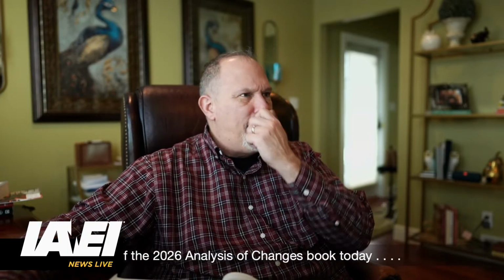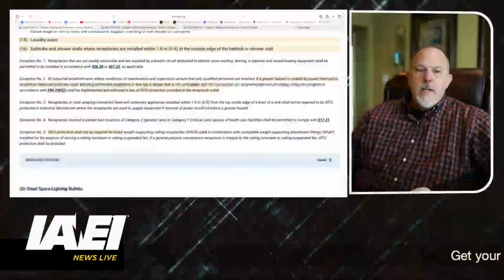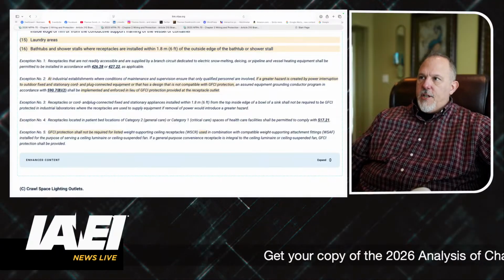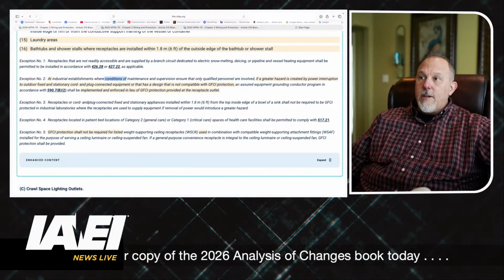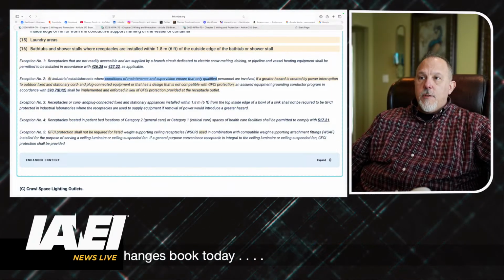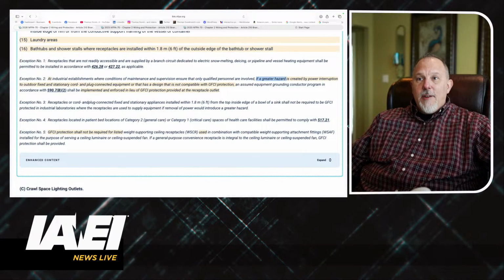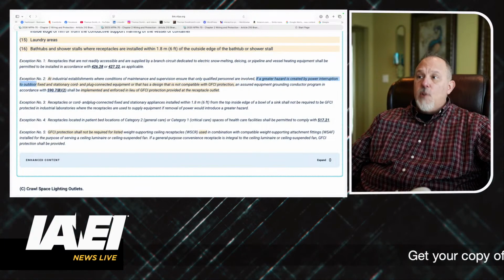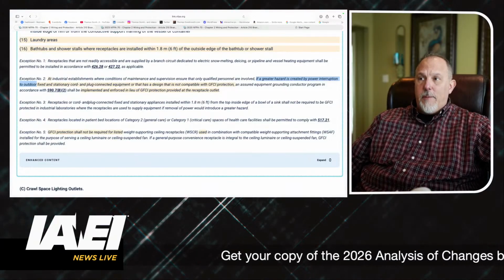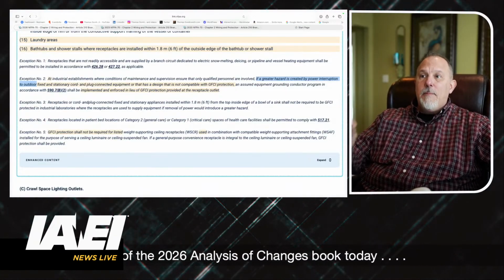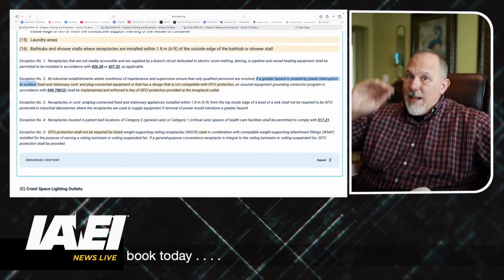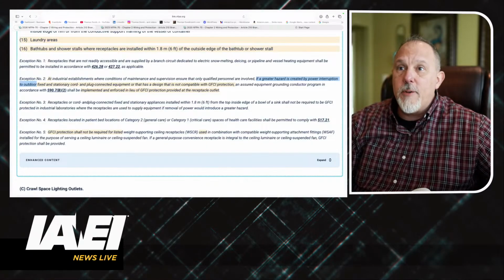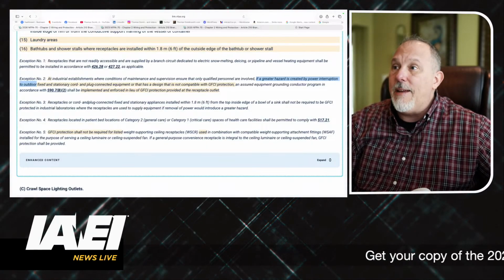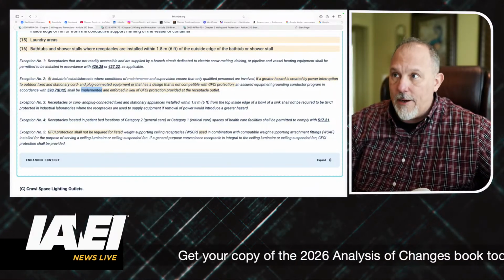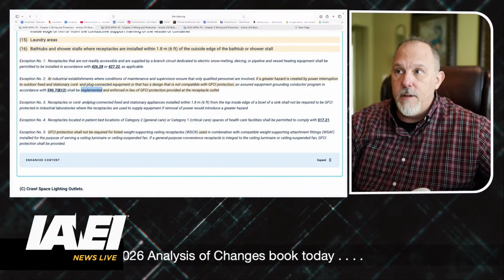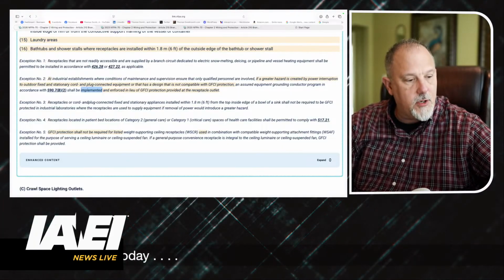All right. And you got to read exception number 2 because it is a good change. It says at industrial establishments where conditions of maintenance and supervision ensure that only qualified people are involved, if a greater hazard is created by power interruption to outdoor fixed and stationary cord and plug connected equipment, or that has a design that is not compatible with GFCI protection, we're limited now to outdoor, and an assured equipment grounding conductor program in accordance with shall be implemented, not permitted, it's now required, and enforced in lieu of GFCI protection provided at the receptacle outlet.